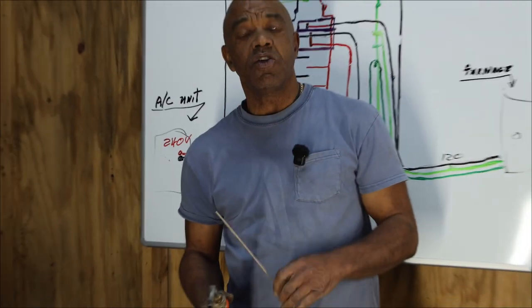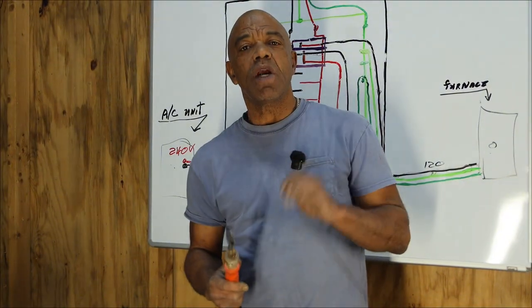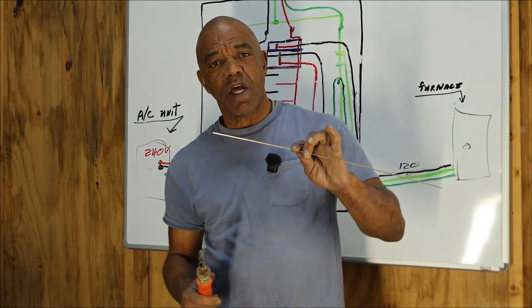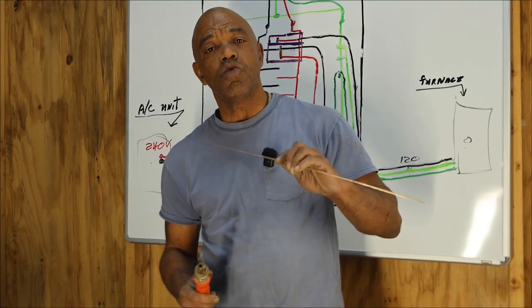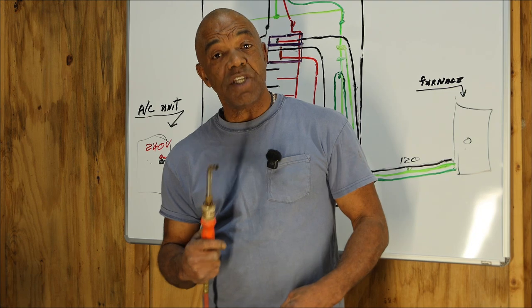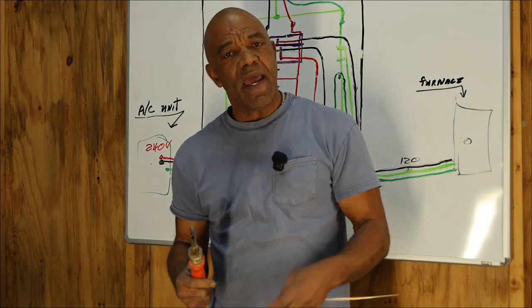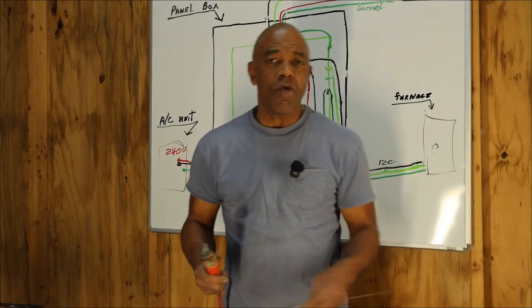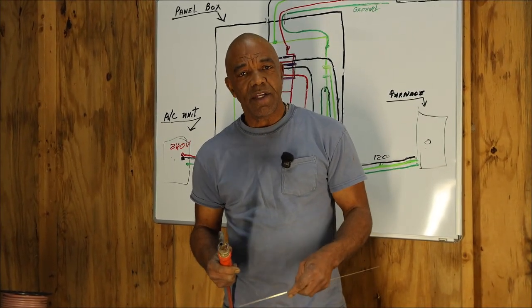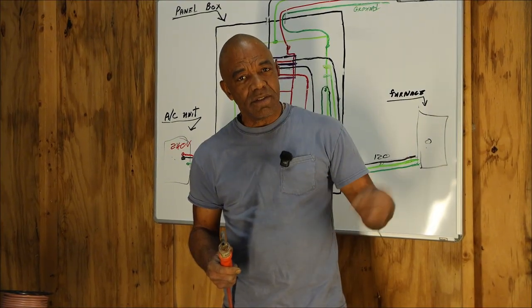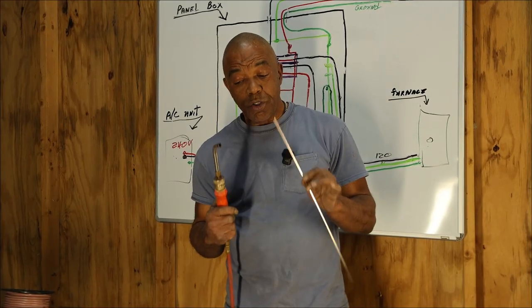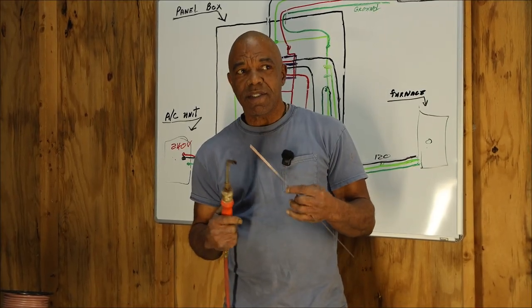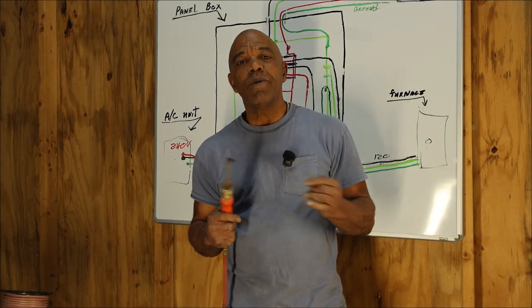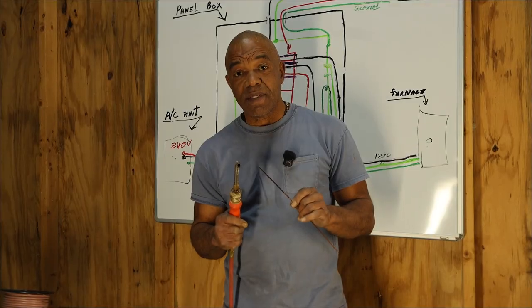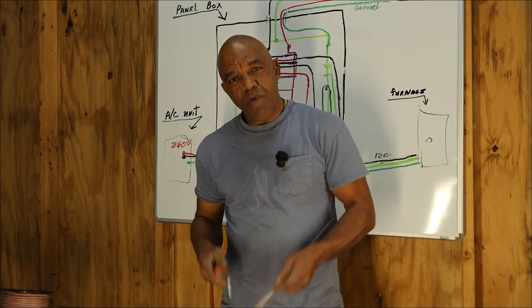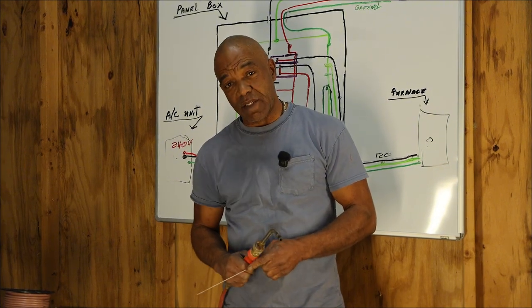It's also important to learn to utilize your heat. You want your brazing rod to melt, but you don't want it to run like water. Too much heat, it'll run too fast. And while it may seal up today, and you don't have a leak when you pressure test, you have a weak connection and it won't be long before it's going to be a leak. So utilizing your torch is a skill and it comes with practice. I can teach you the method, but you are going to have to get practice working on it in order to perfect it. All right?